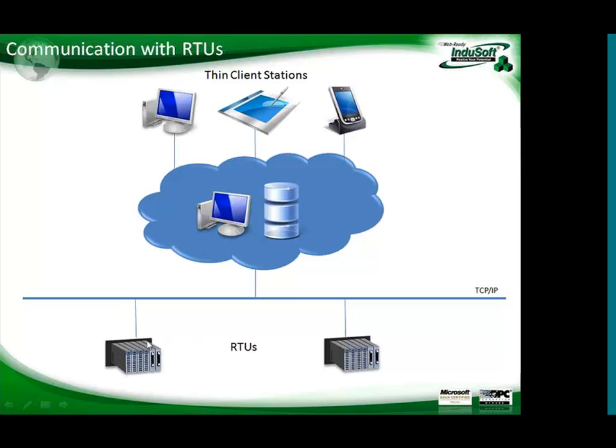InduSoft Web Studio running on this virtual server on the cloud would be able to run the native drivers from InduSoft or even the OPC interfaces, OPC UA, OPC XML, all the modules available in InduSoft, and communicate with the RTUs. All you need is a TCP/IP link between InduSoft Web Studio and the actual RTUs.